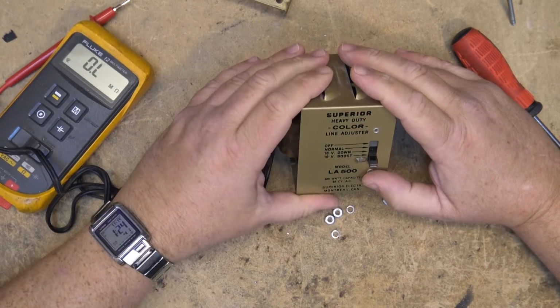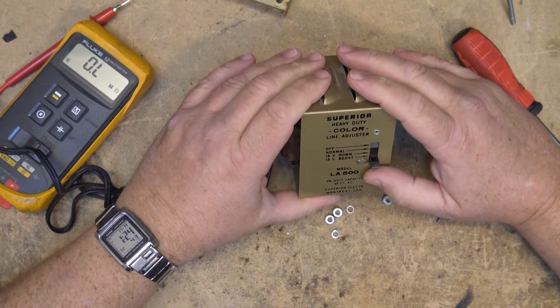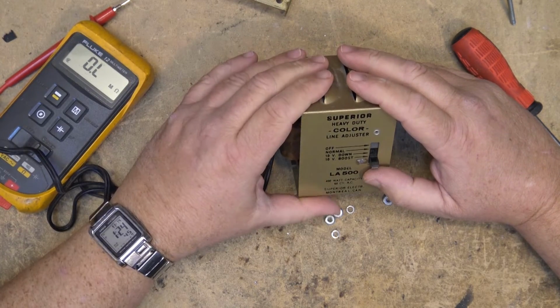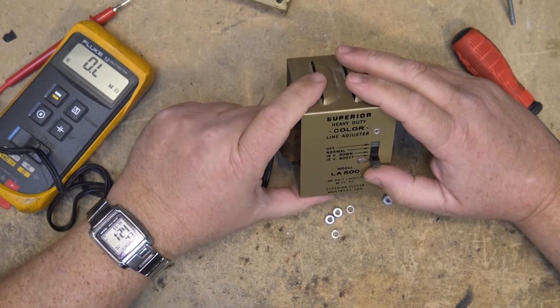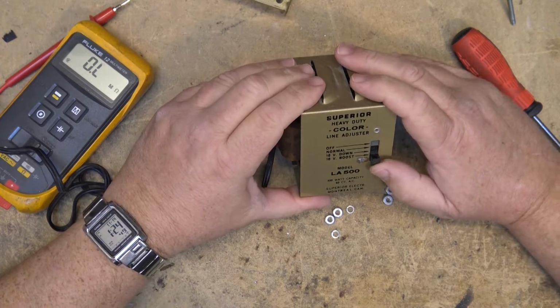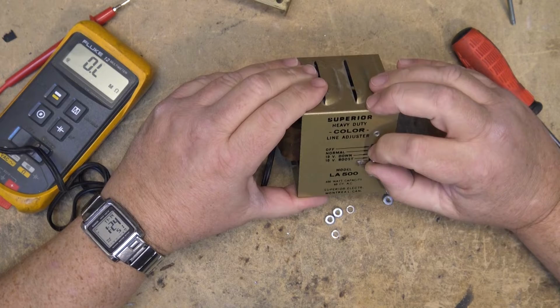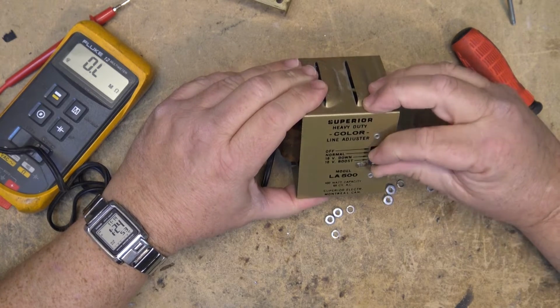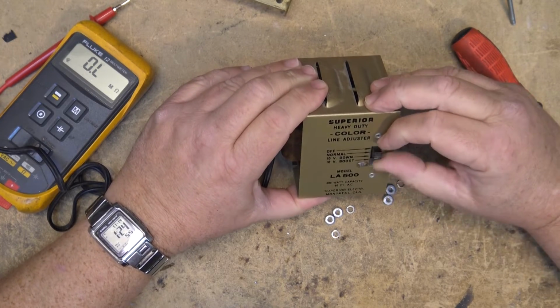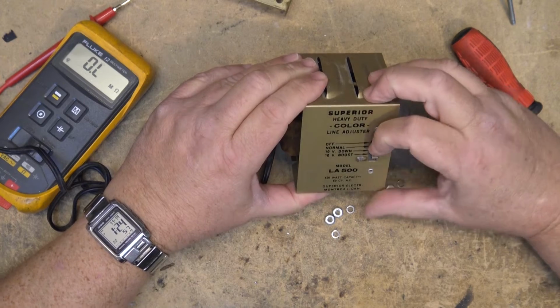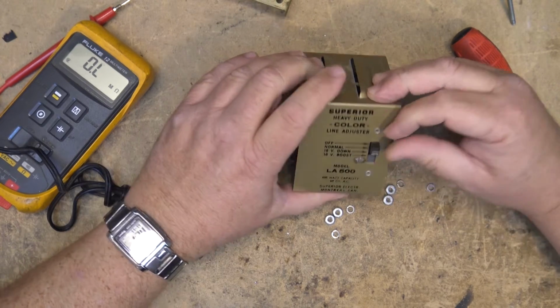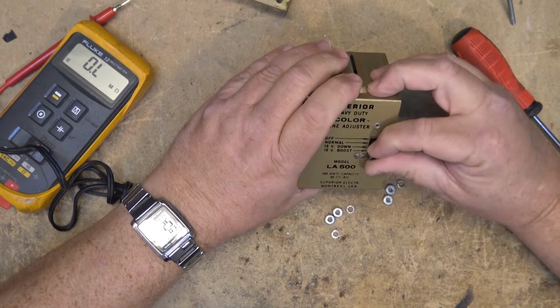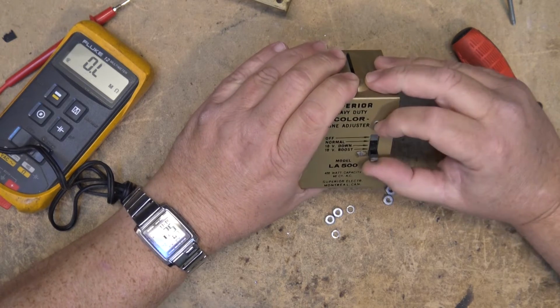And that would restore the width of their picture. Or in off-peak times, when people weren't cooking dinner, if you were close to the substation or close to the distribution transformer, your voltage might be a little too high, so then you could turn your voltage down. This way you had a three-way position: normal, 10 down, and 10 boost, and off. You could actually shut the power off. So: normal, 10 down, and 10 up.